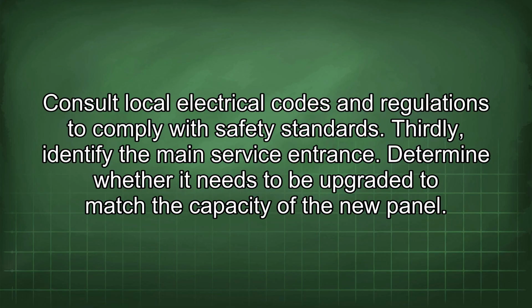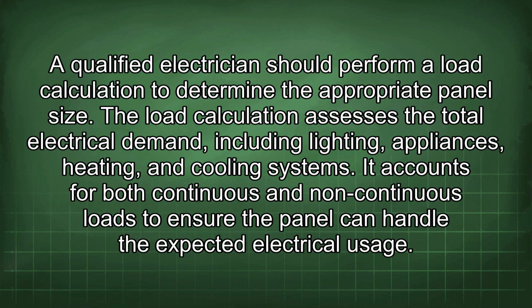Thirdly, identify the main service entrance. Determine whether it needs to be upgraded to match the capacity of the new panel. A qualified electrician should perform a load calculation to determine the appropriate panel size. The load calculation assesses the total electrical demand, including lighting, appliances, heating, and cooling systems. It accounts for both continuous and non-continuous loads to ensure the panel can handle the expected electrical usage.